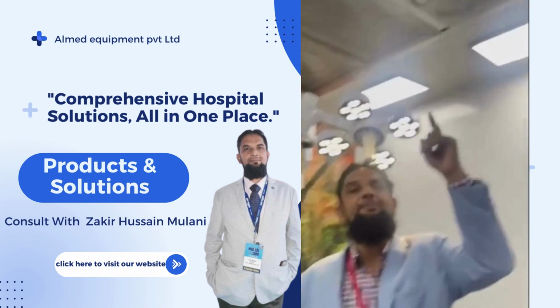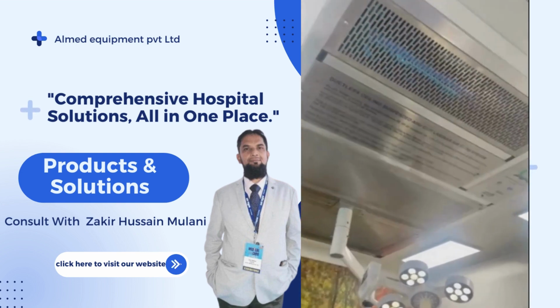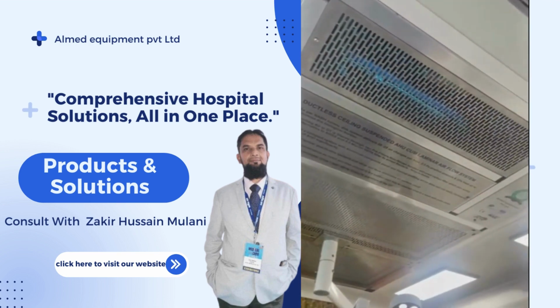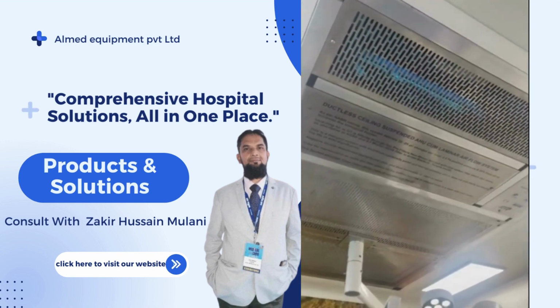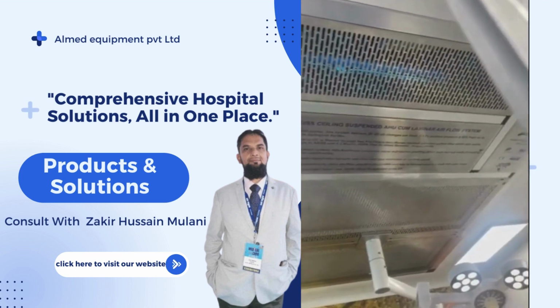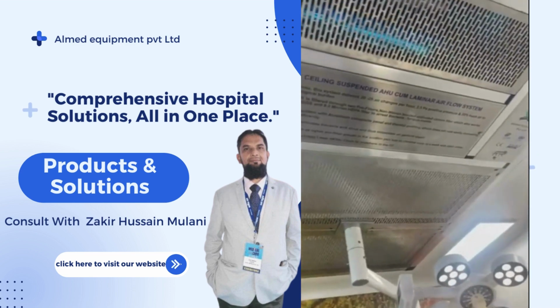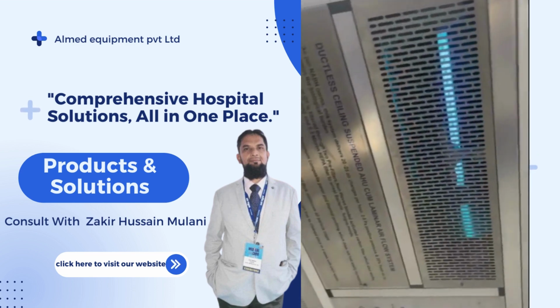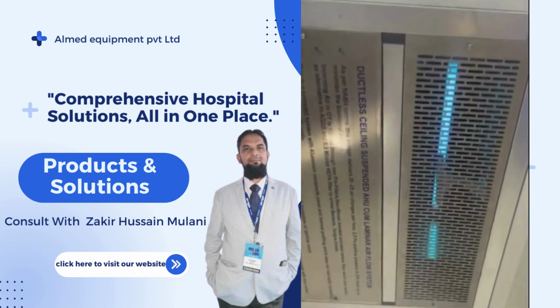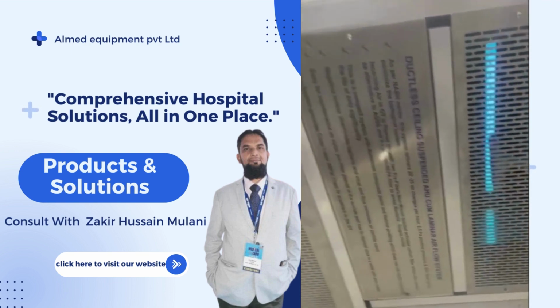This is the ceiling suspended AHU with Laminar flow. From the ceiling to the false ceiling, just 1.5 feet distance is required, just 18 inches. So this can be installed anywhere, not only in the operation theatre, but any place where you want infection control.